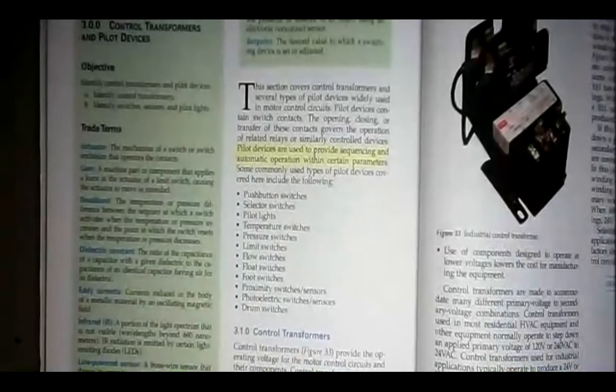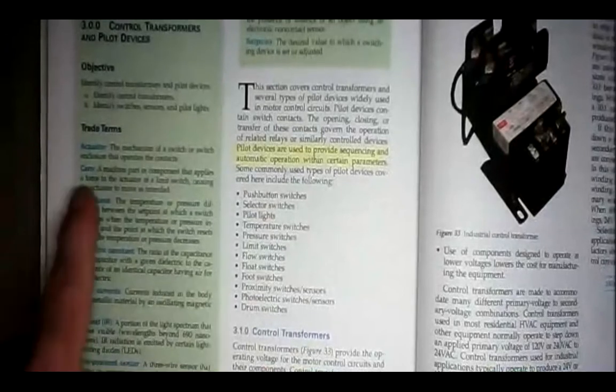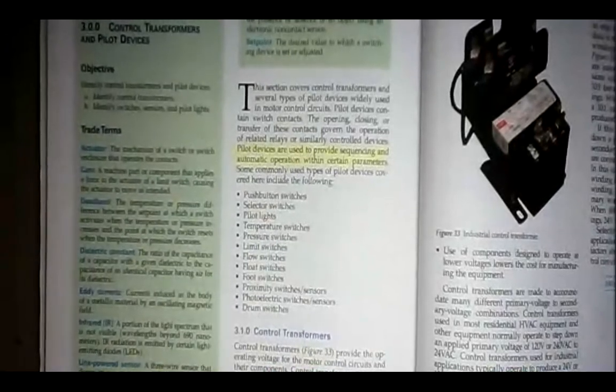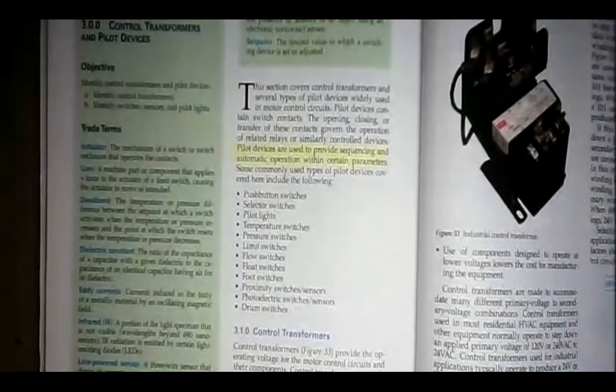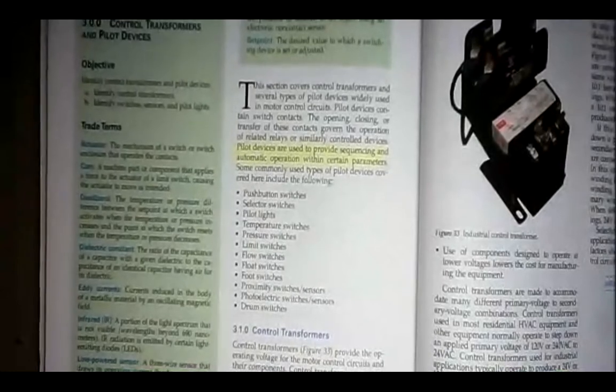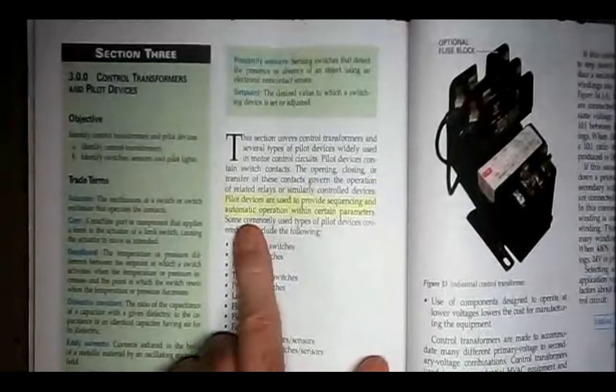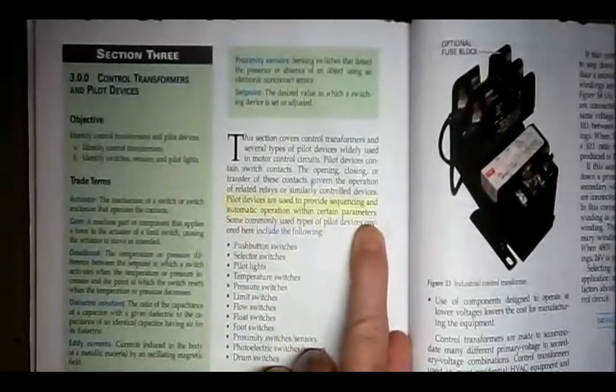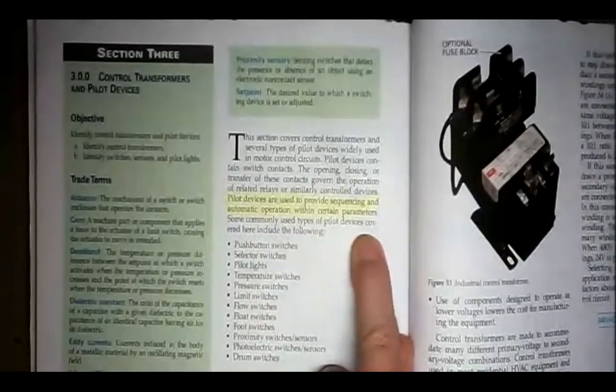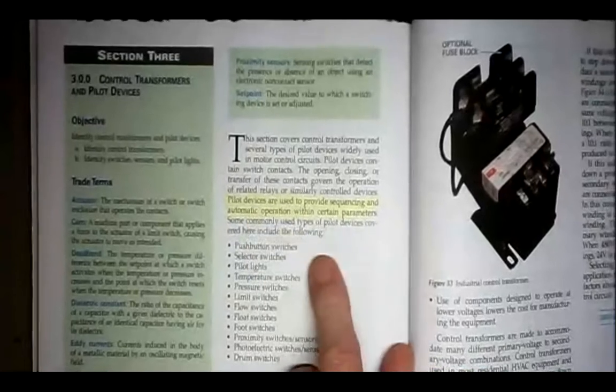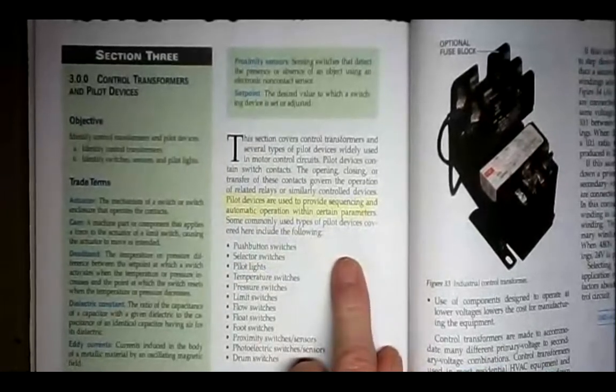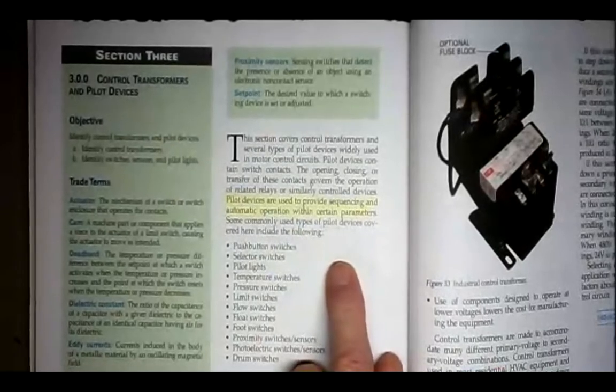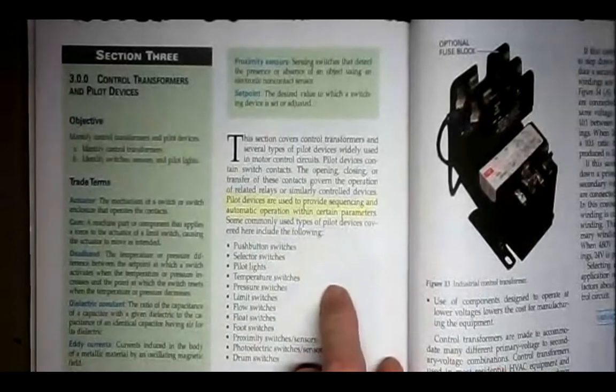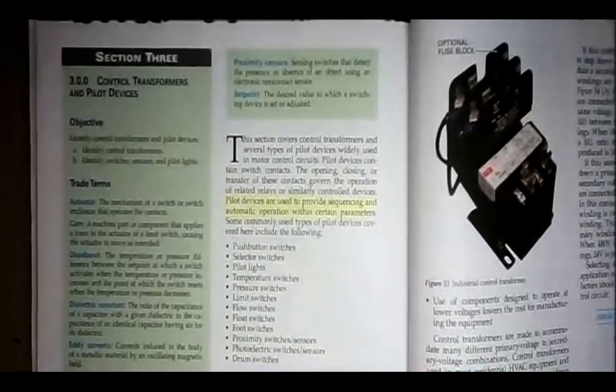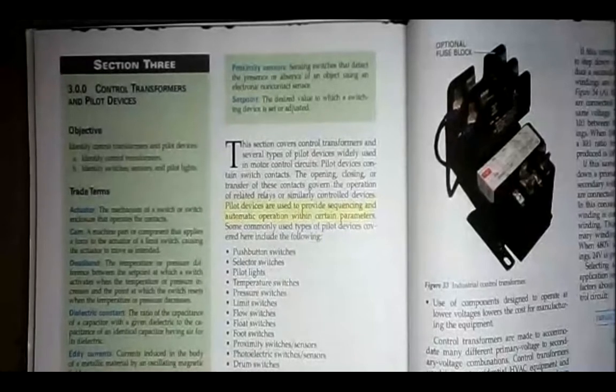Okay, on page 32, again, they have more trade terms. You should go in and read those trade terms. They're very good. They give you a lot of information. On the right-hand side of page 32, first paragraph, it says, pilot devices are used to provide sequencing and automatic operation within certain parameters. So pilot devices can be push buttons. They can be timers. They can be proximity switches or temperature switches or level switches, float switches if you're talking about fluids, anything like that. Those are pilot devices that will aid in the controlling of an operation.